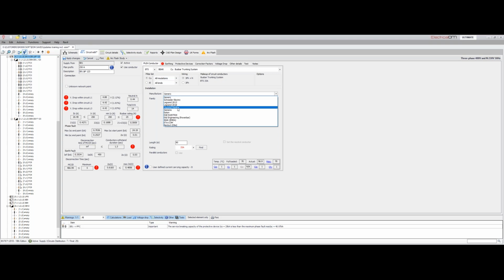The information is a lot of the time manually inputted. We have been working with other manufacturers, particularly where we come to things like protective devices. So we have links in with the likes of Schneider, who we have access to their own software with various information and curve data around protective devices, so we're able to take that data out and put it directly into the software. The same is with things like Siemens as well, where we're looking at their system like SIMARIS. And other manufacturers are producing data in XML formats that we can hopefully bring in directly into the software later on, using what we refer to generally as an API of information. So there's a standardization to how that data is laid out, so we can easily incorporate it when necessary.